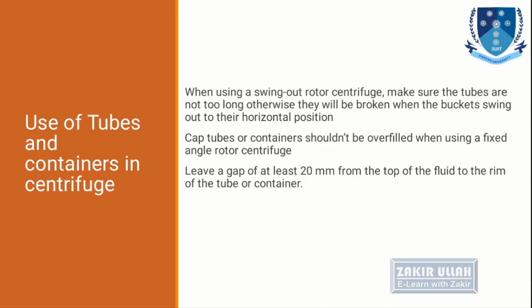At least a 20 millimeter gap should be present on each tube when we are centrifuging a solution in a tube, because this space gives the solution room to adjust during centrifugation, if the solution moves up or down, so that the solution does not cross the level of the tube and does not destroy or infect our centrifuge.